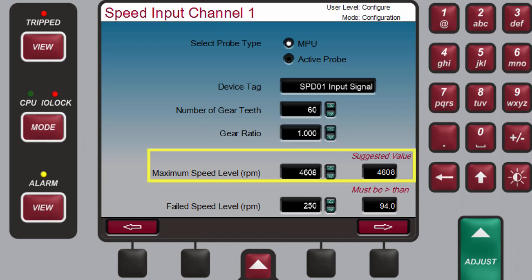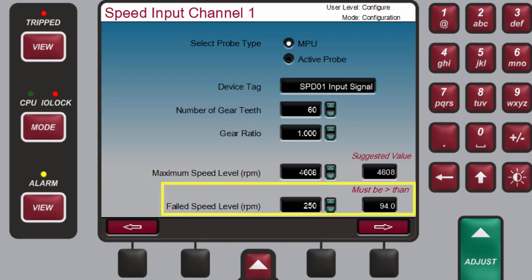The highest speed that the controller will read — if the speed goes above this level, it will not be read into the control. And the failed speed level, which is used to determine when a speed probe has failed. If the speed drops below this level, the control will determine that the speed input channel has failed and will issue an alarm. If all speed inputs fail, the 505 will issue a trip on loss of speed inputs.